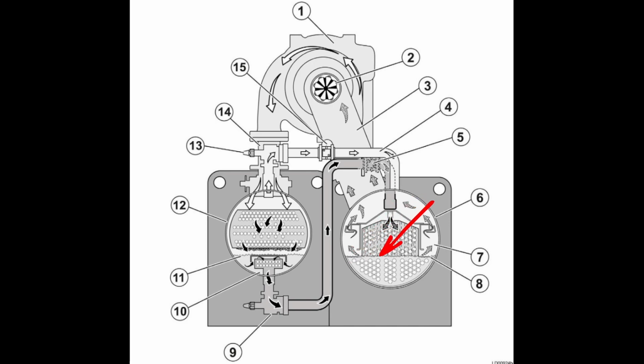Refrigerant boiling off, especially at high load and creating a little bit of a boil film, is normal to some degree. It's usually not very heavy or excessive, though. So when you start to see really heavy foaming during normal operation, and especially if it has a color tint, then that's when you should start being concerned about your oil stacking a bit heavy in the evaporator, and whether or not your eductor may be functioning properly, or if you're having other kinds of migration issues or anything of that nature.